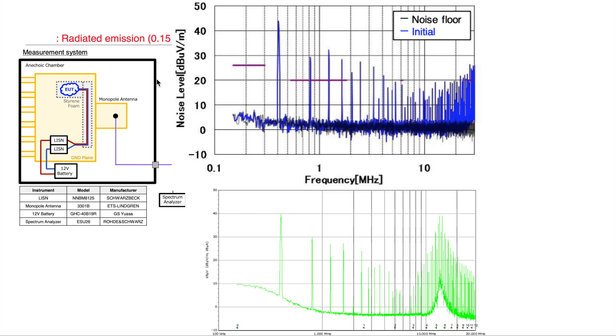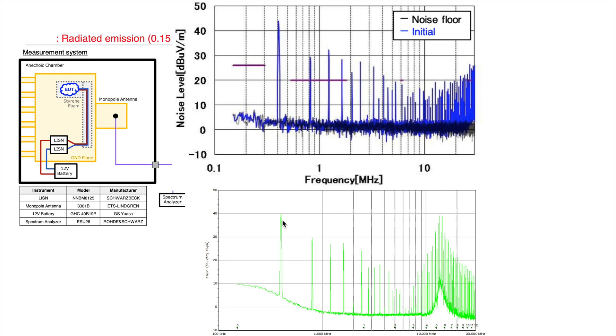Let's have a comparison between our tent results with the accredited test house results. On top is the test house results, on bottom is our tent miniature antenna results. As you can see, the overall profile generally looks very similar. The first order harmonics we have about 5 dB difference between the two results, which is not too bad. From the second order harmonics the profile shows very similar trend.